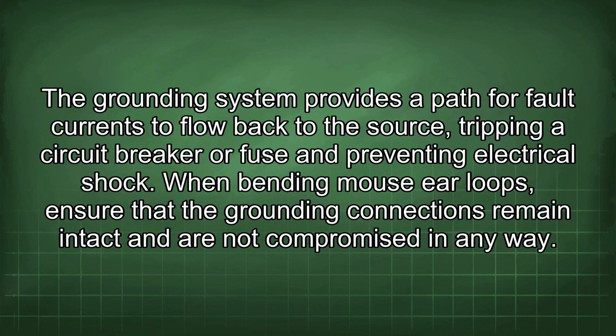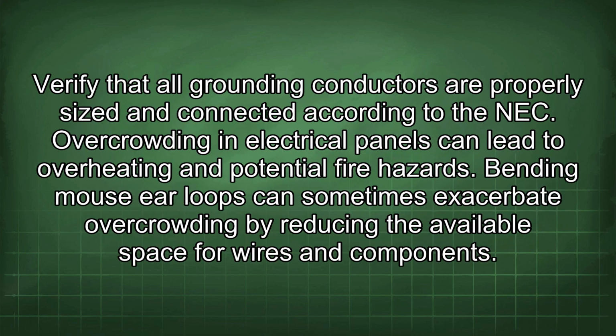When bending mouse ear loops, ensure that the grounding connections remain intact and are not compromised in any way. Verify that all grounding conductors are properly sized and connected according to the NEC.